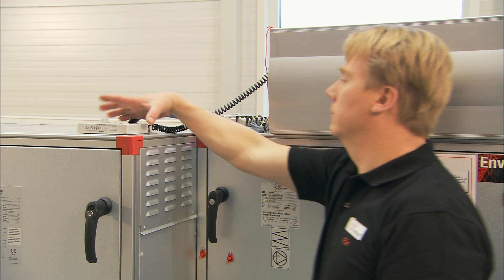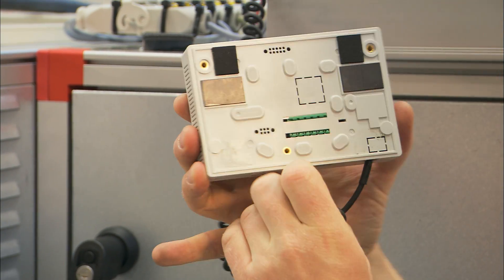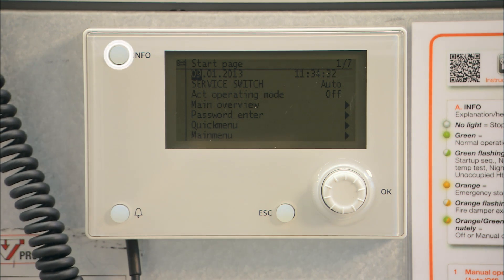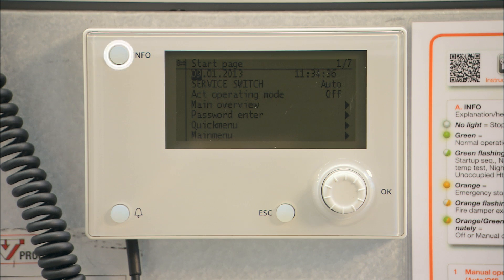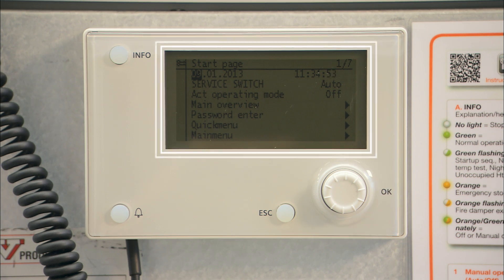Access the IV Produkt hand unit that is used to control functions and read off settings and values. It has a magnetic back, so attach it at a suitable working height or hold it in your hand. The unit has an information button which when pressed shows the current status of the air handling unit, an alarm button, and an escape button used to navigate back through the menus or to cut short the ongoing editing of a value. Use the navigation dial to navigate through the menus and change values by turning the dial. The display enables you to read off the information.